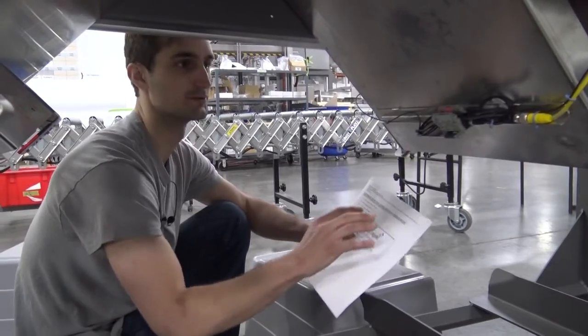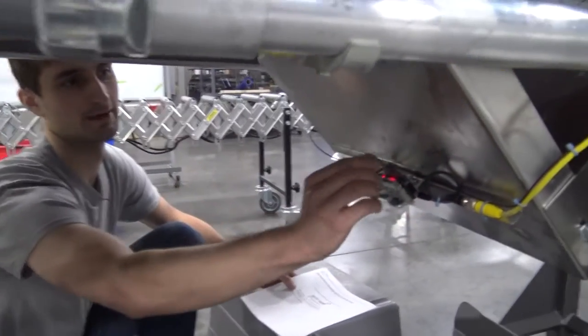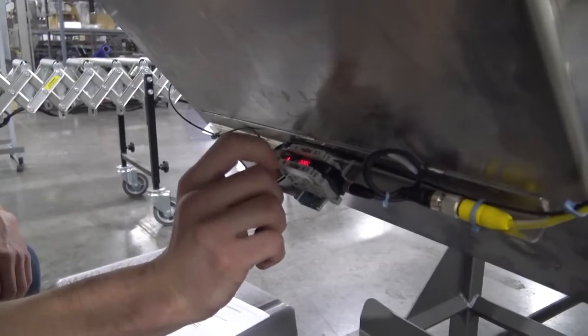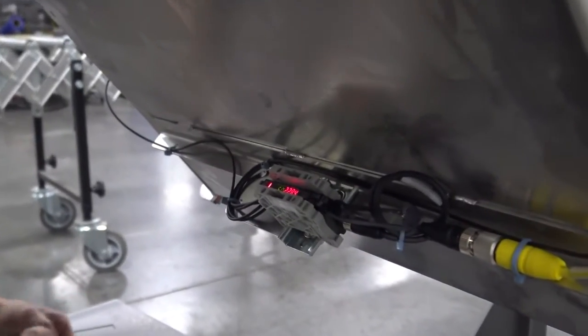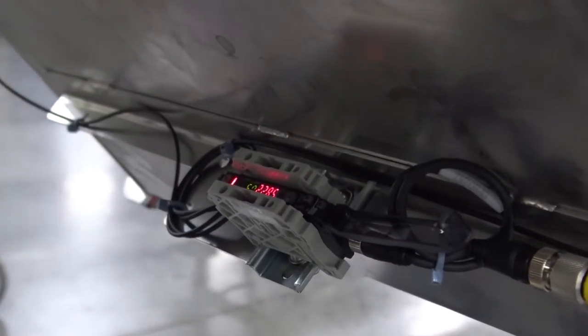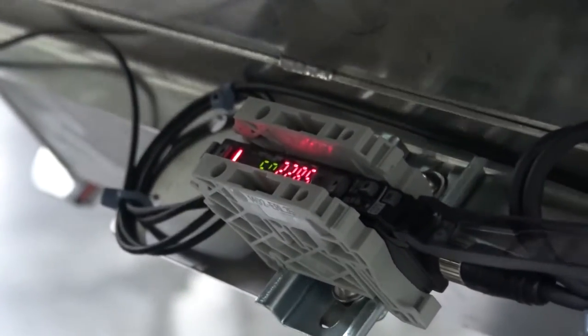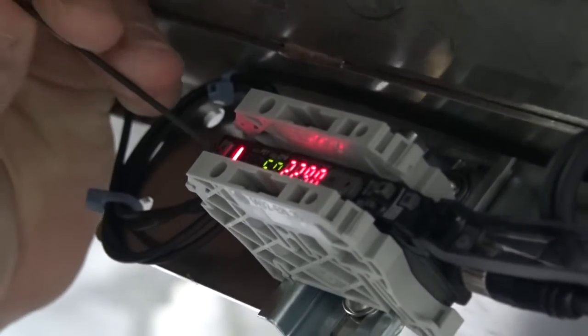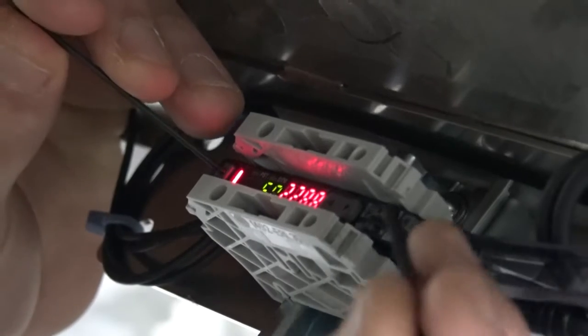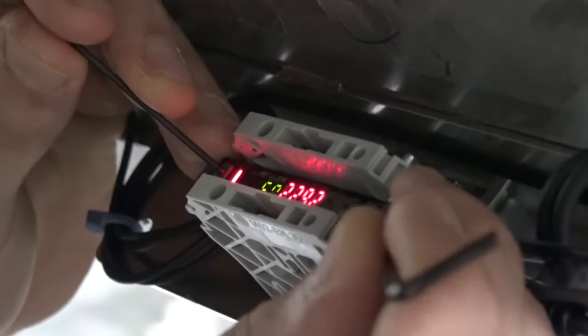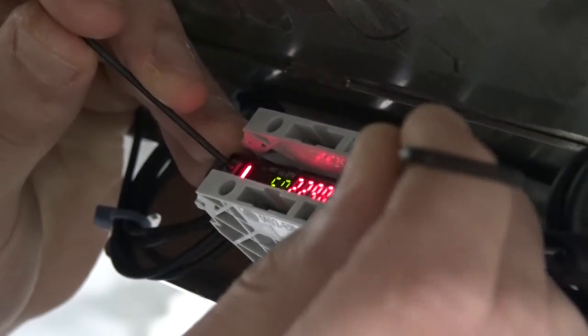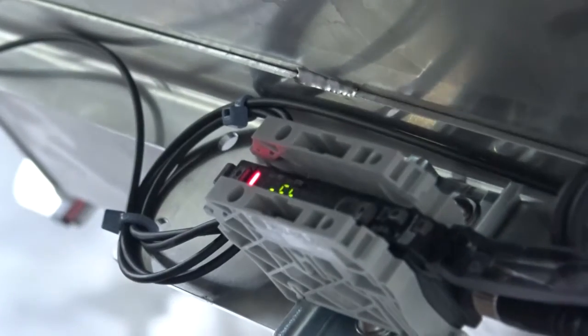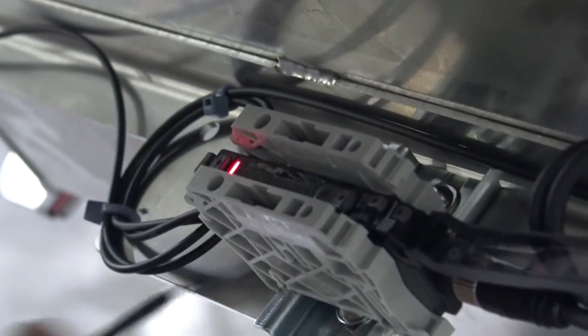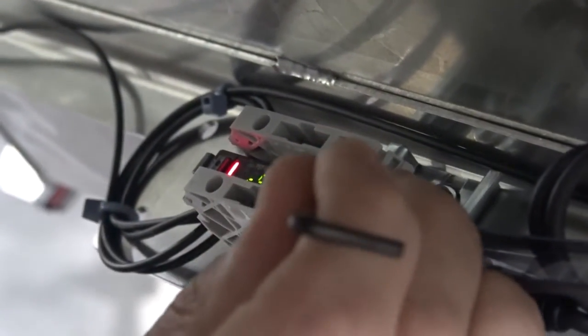So first thing to do is reset the sensor. You have this little Lexan cover. You're going to pop it open. And to reset, you're going to press set and preset simultaneously for 3 seconds. Set right here on my left, and preset on the right. Press those at the same time for 3 seconds. And I got a flashing reset button. I'm going to press the mode button to accept that reset.